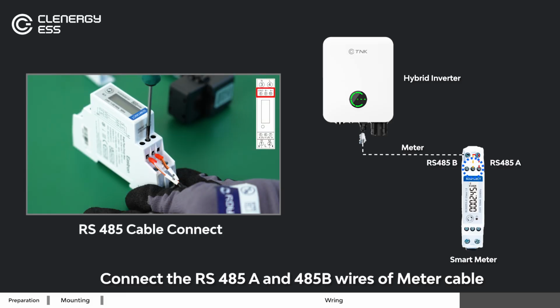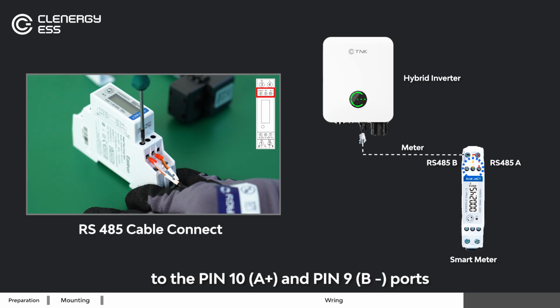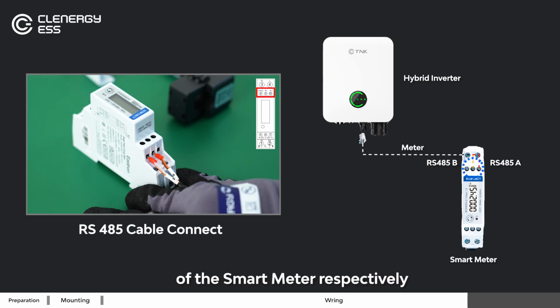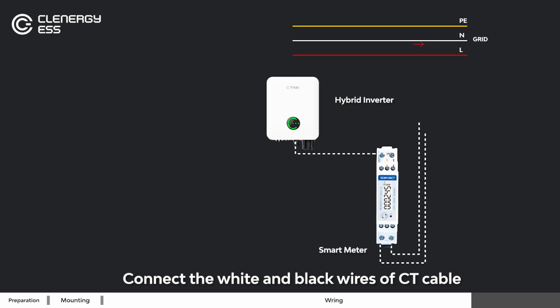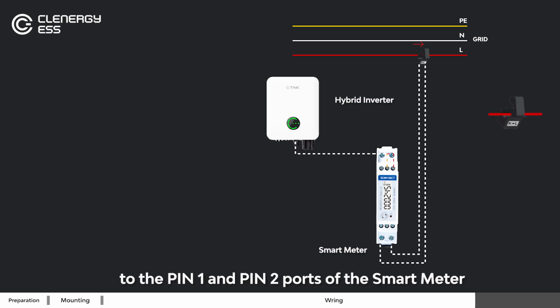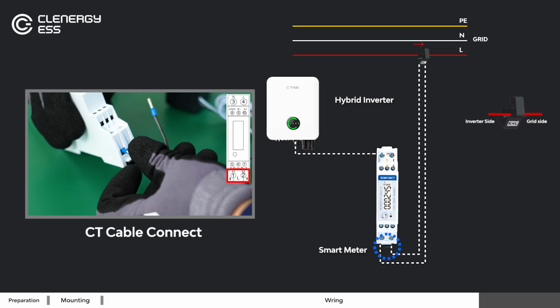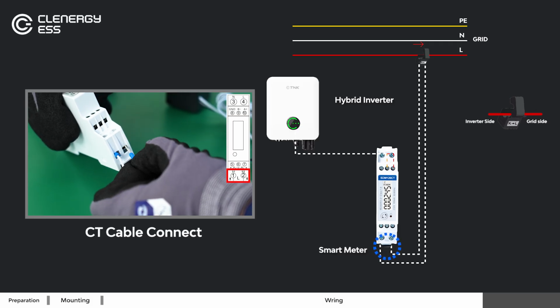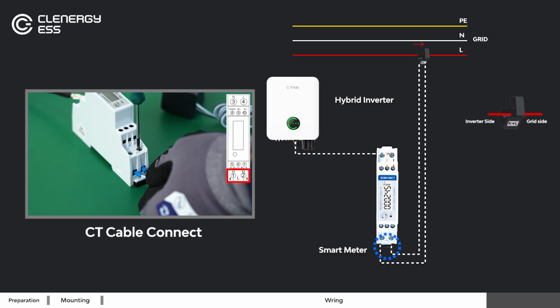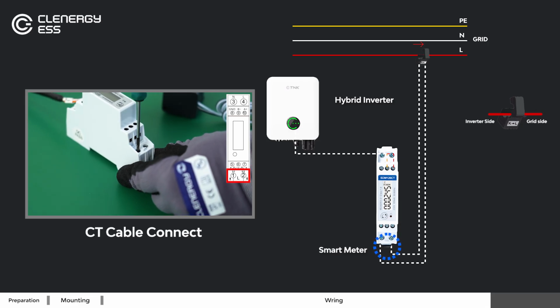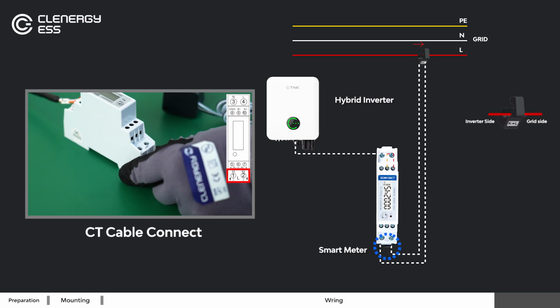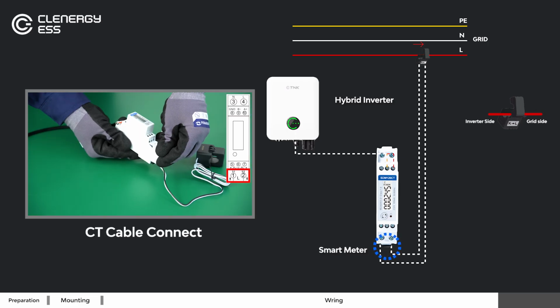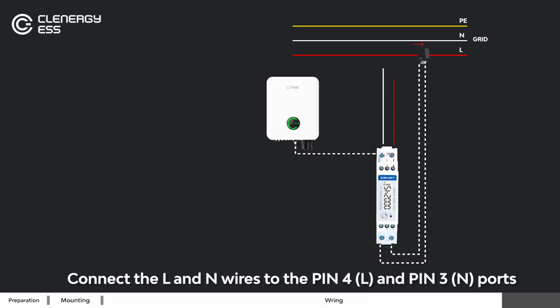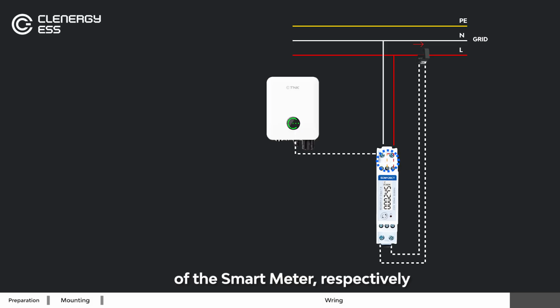Connect the RS485A and 485B wires of meter cable to the pin 10 and pin 9 ports of the smart meter respectively. Connect the white and black wires of CT cable to the pin 1 and pin 2 ports of the smart meter. Connect the L and N wires to the pin 4 and pin 3 ports of the smart meter respectively.